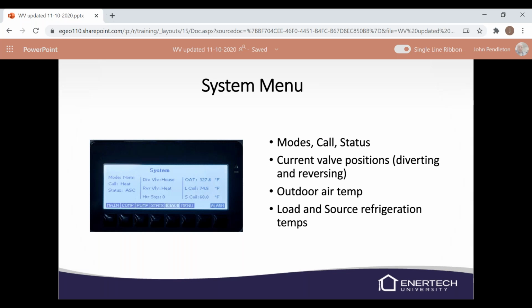The system menu will show the call, or the mode. It'll also show whether it's a normal mode, test mode, manual mode, emergency mode, and your call, whether that's heating, cooling, or DHW, domestic hot water. It'll show you your status, which this happens to be in a short cycle. It'll say run, idle, startup, ASC.